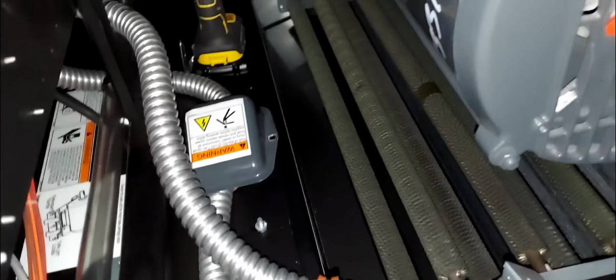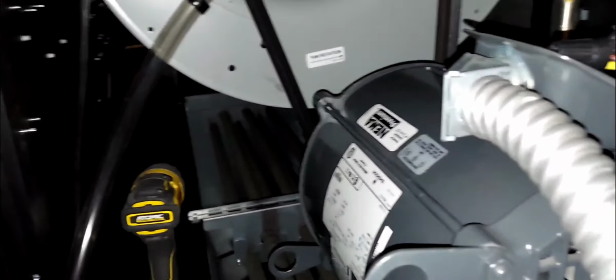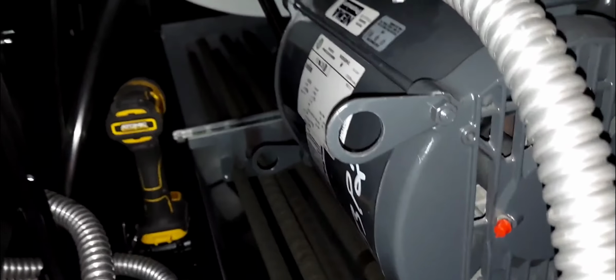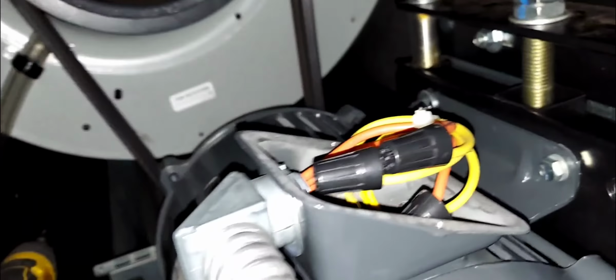All right, so bear with me. We're doing this troubleshooting in real time. I suppose I could just press this button and reset it, but I don't want to do that because I got the panels open. All right, so I want to button everything back up, and then I'm just going to check that overload contacts, and then if the contacts are open, I'll hit the reset, measure the amperage. I'm going to check the windings of the motor, but I'll do it from the fan contactors because you don't have to do it right here.